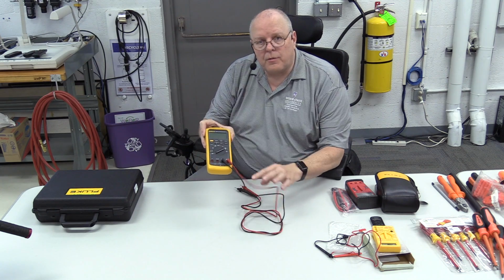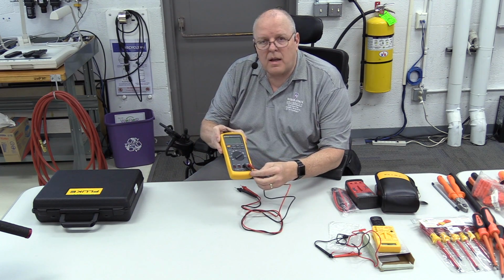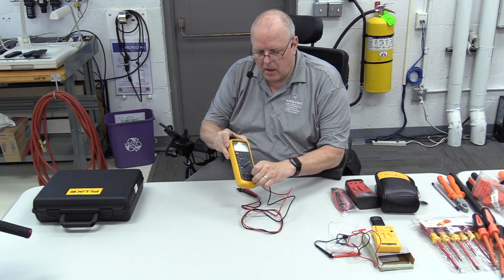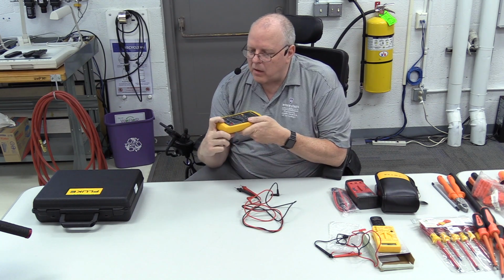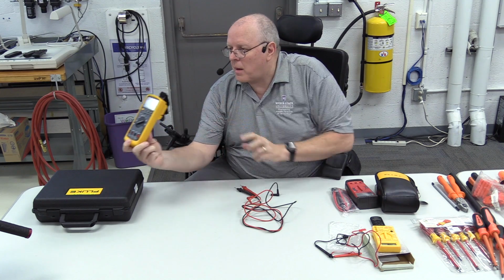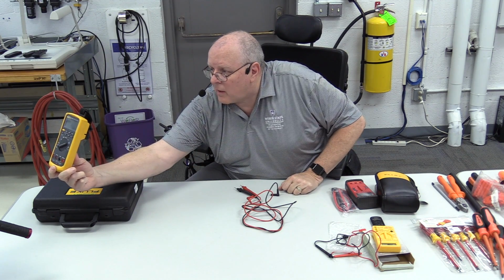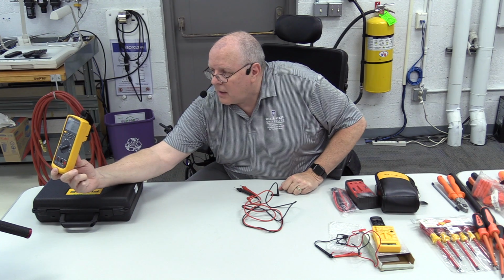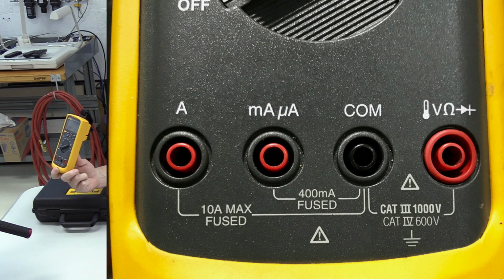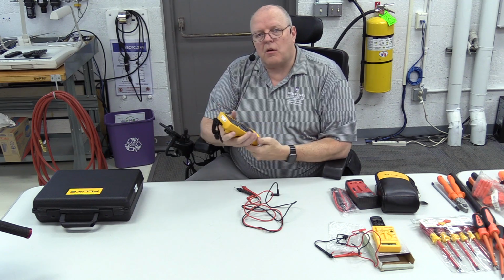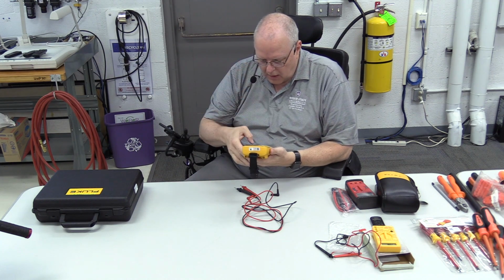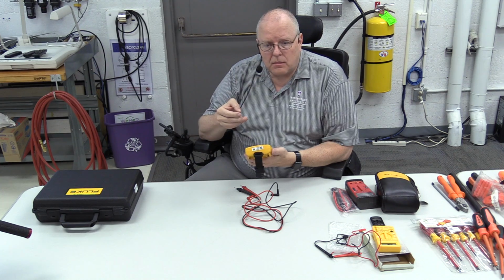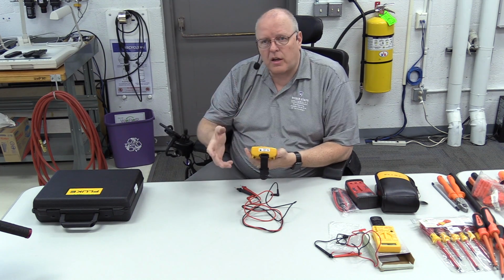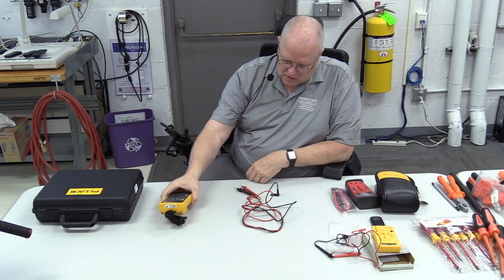All right, the Fluke 87 meter is rated as a Category 3 meter. If we look right on the front of the meter, between the black input terminal and the red input terminal to the right of it, it reads Category 3, 1000 volts. That means this meter, held in your hand, can handle 1000 volts without burning itself up, without shocking you through the meter case itself.